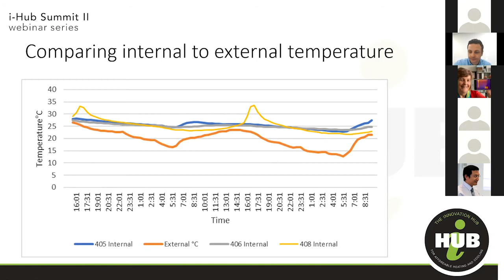Now, because that test was conducted in September, it was still cold back then. So you can see the temperature can get quite low during nighttime, but you can see that the performance of the envelope was quite good. It kept the 3 rooms more or less stable during that time. But that also indicates that the majority of the heat gain was through the windows, through the glazing. So it might be a good idea to test the impact if we were to add some shade to the glazing areas.